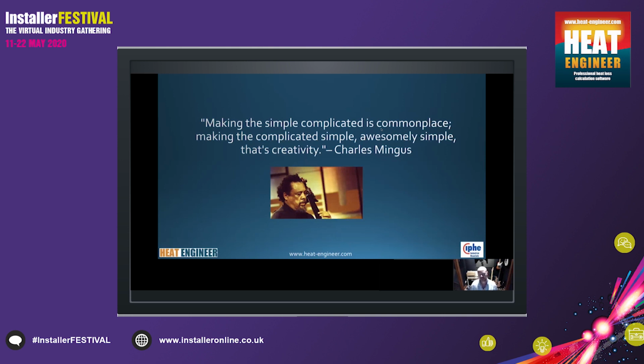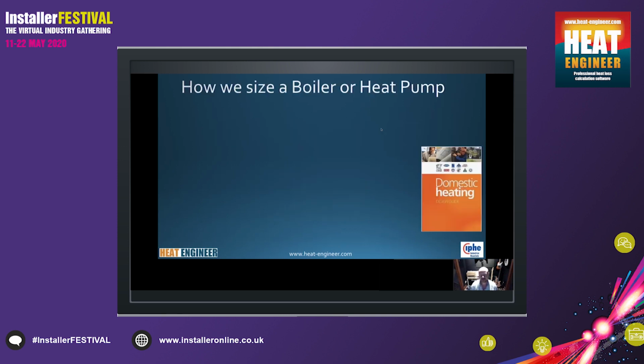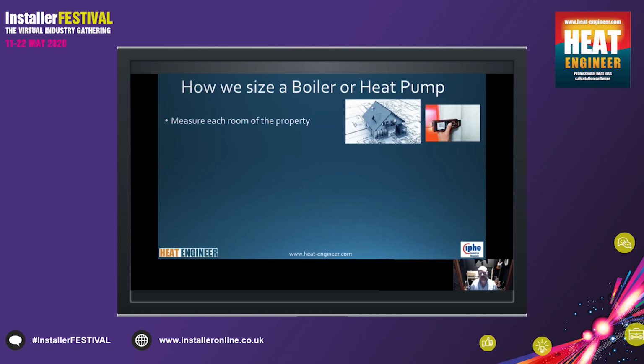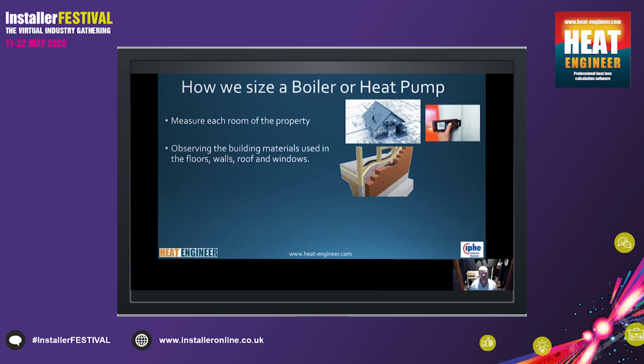There's a couple of things that we try and push of simplifications. I won't read this out. Everyone can read that on their own on this screen. But how do we size a boiler or a heat pump at the moment? Well, we measure each room of the property, as we're showing, with a laser measure, or say from drawings. We observe all the building materials that we have in the roofs, walls, floors, and windows, etc., and try and record them and work out exactly what it is that is needed.